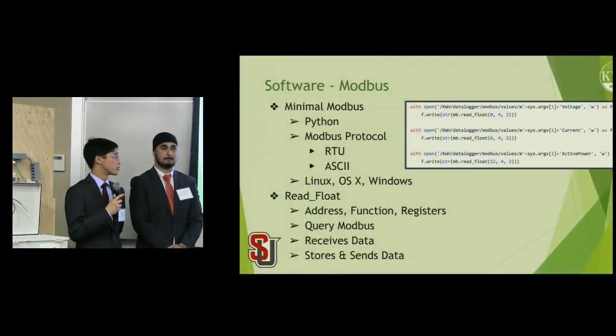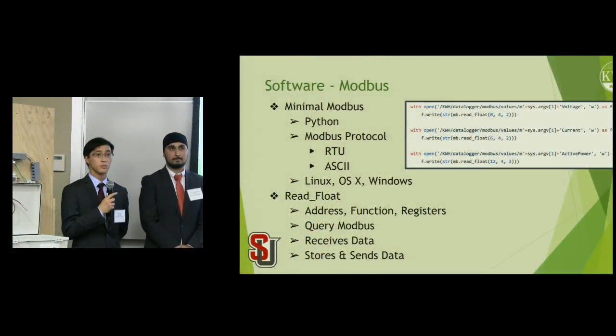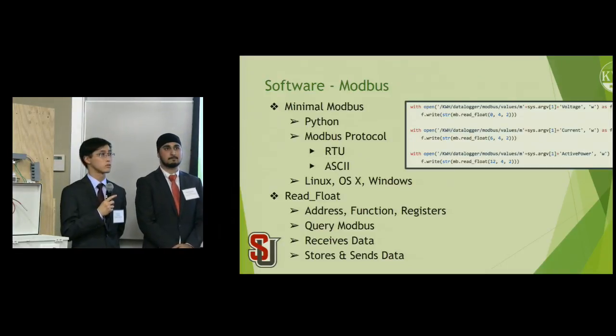Specifically, we're using the function called readFloat, which has 3 parameters: the register address, which is the address of the Modbus; the function code, which is the data point you're querying; and the number of registers, which is 2 for these meters. So the Raspberry Pi queries the Modbus with the function readFloat, and in return the Modbus sends the data point back to the Raspberry Pi, which is processed on the Pi and then sent to the Grafana website we're sending data to.